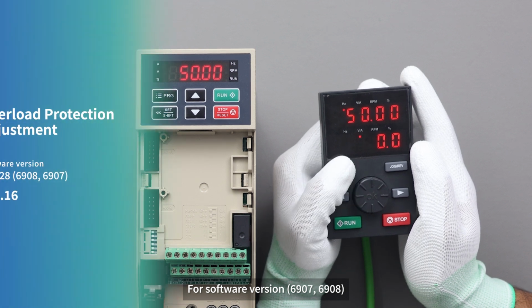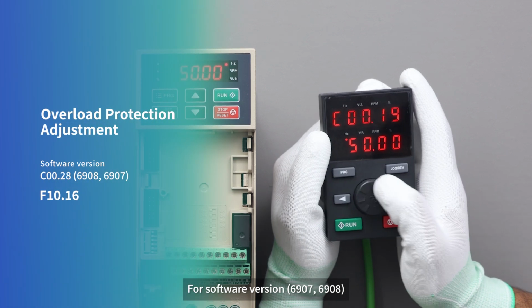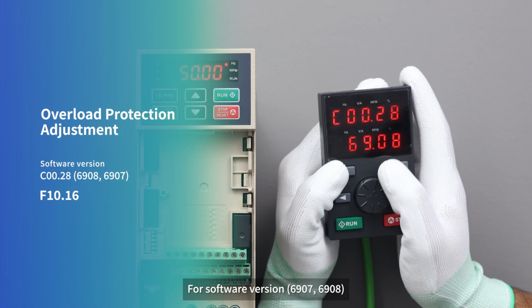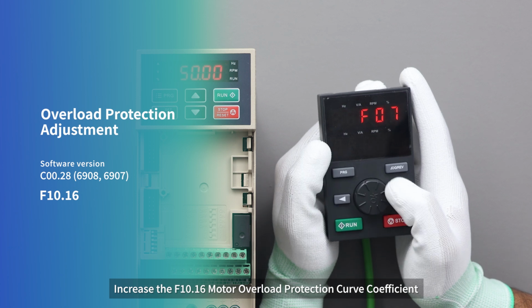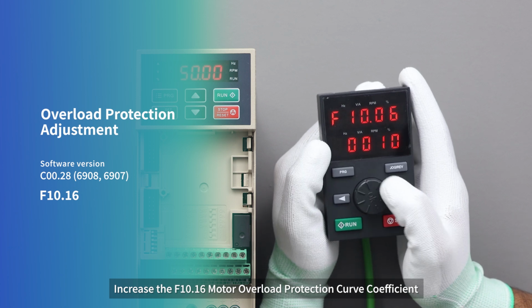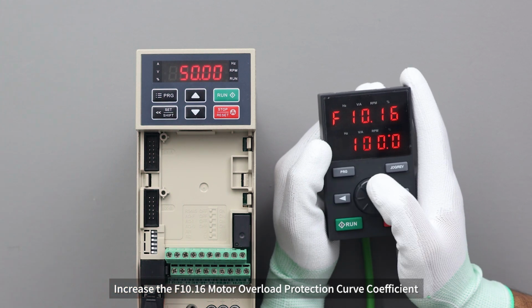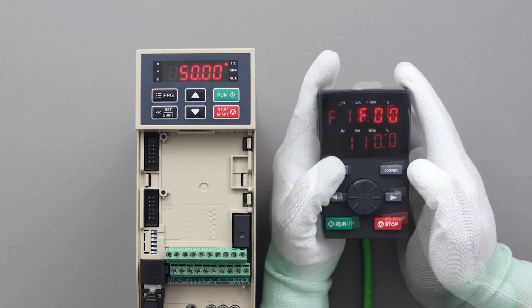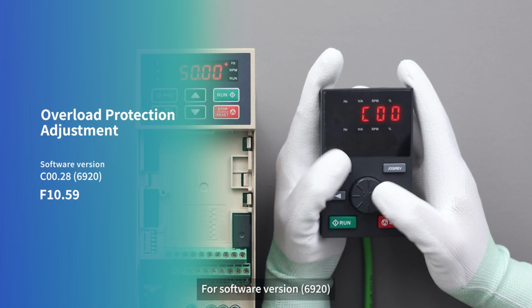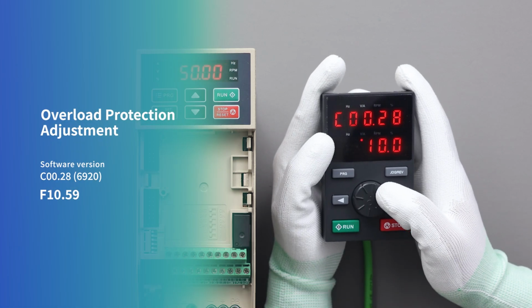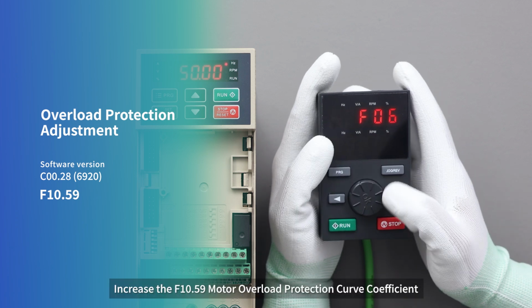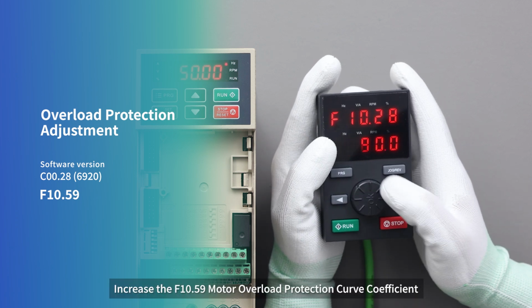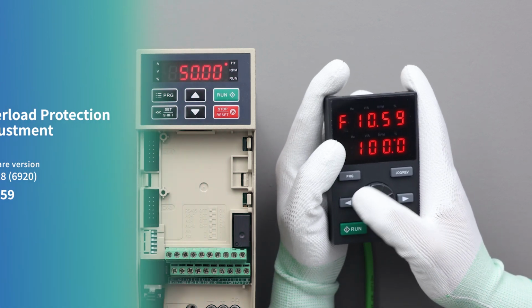Overload protection adjustment. For software version 6907 and 6908, increase the F10.16 motor overload protection curve coefficient. For software version 6920, increase the F10.59 motor overload protection curve coefficient.